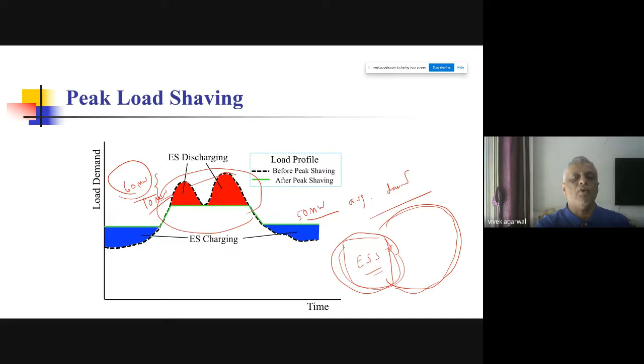So as you can see here, this ESS application, as far as this particular example is concerned, is called peak load shaving. It is able to shave off this extra load on the microgrid by supplying power during that time. You can see this is the time when the energy storage is discharging, and this is the lean period, when there is not much power demand, when the energy storage is being charged. So you charge it during the lean period, and then during the peak demand, which peaks up to 60 megawatt, you let the ESS give energy to the system. That is how you can handle this situation.